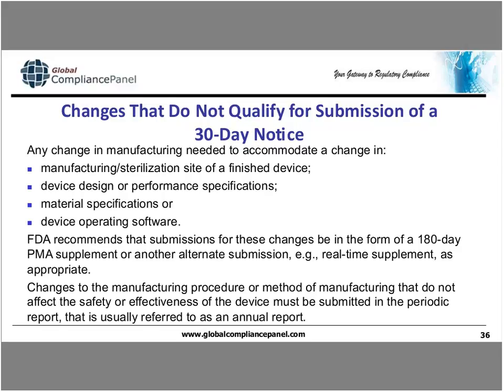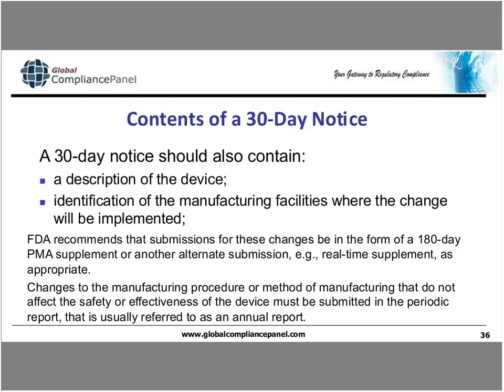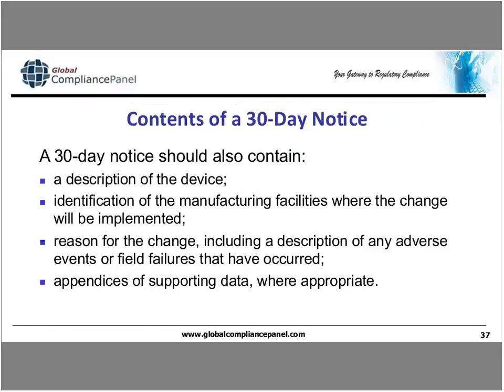Changes to the manufacturing procedure or method of manufacturing that do not affect the safety or effectiveness of the device must be submitted in the periodic report, referred to as the annual report. The contents of the 30-day notice: a description of the device, identification of the manufacturing facilities where the change will be implemented, reason for the change, including a description of any adverse events or field failures that have occurred, and appendices of supporting data where appropriate.